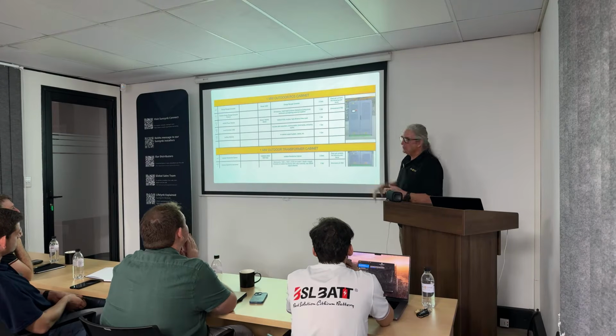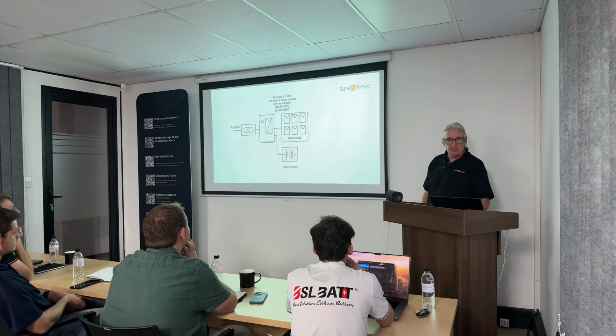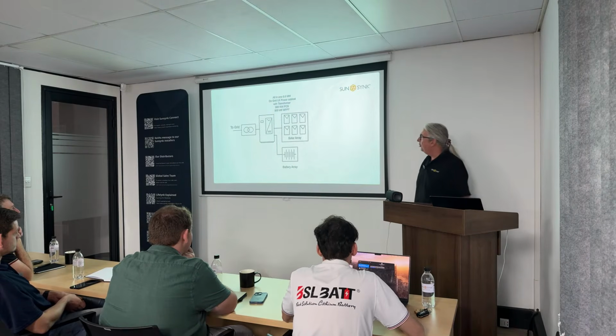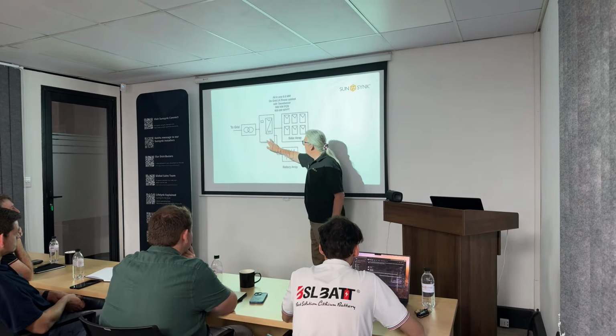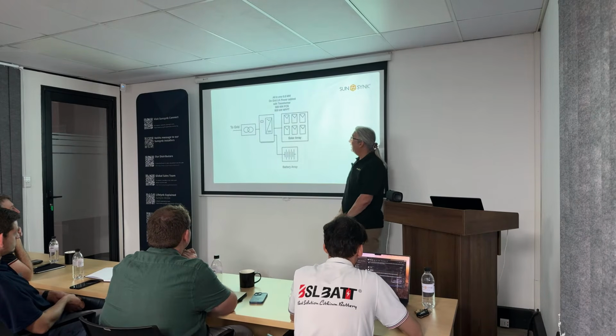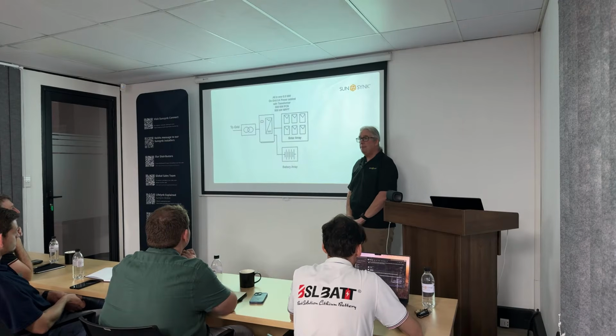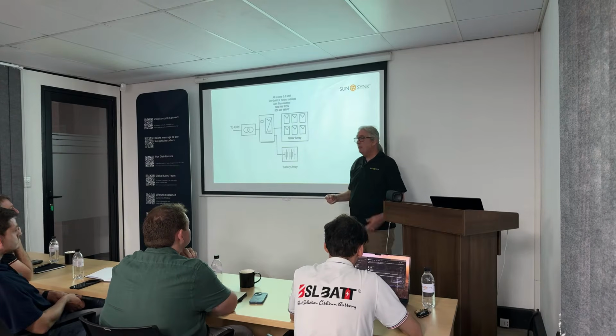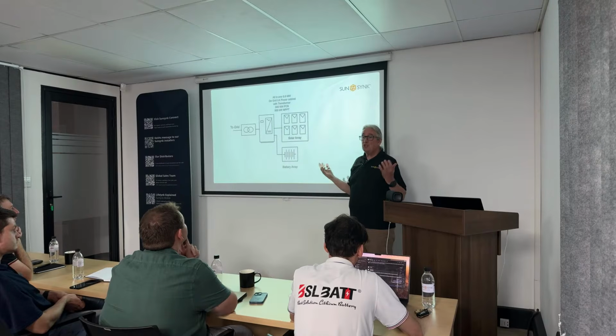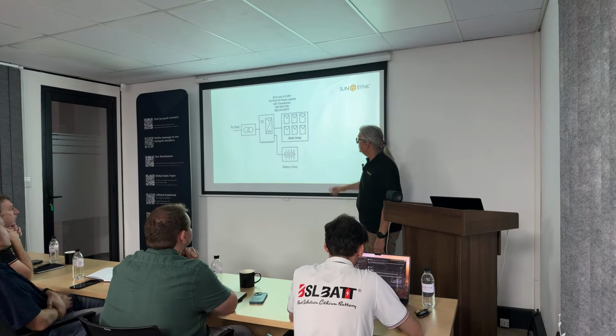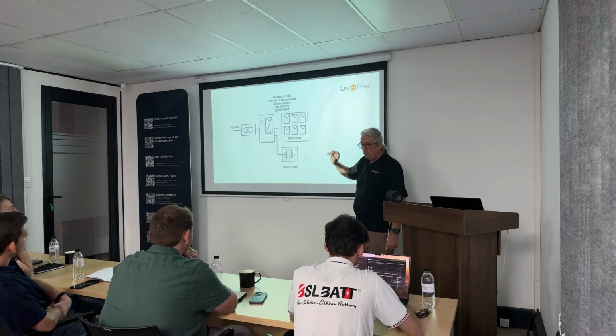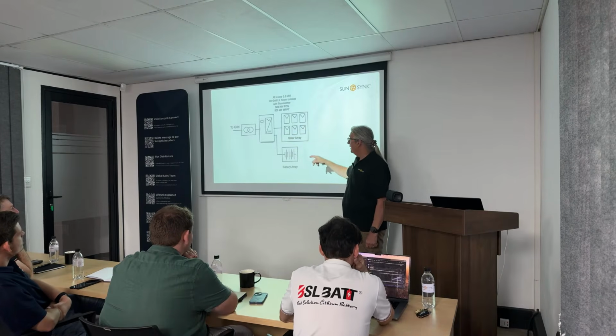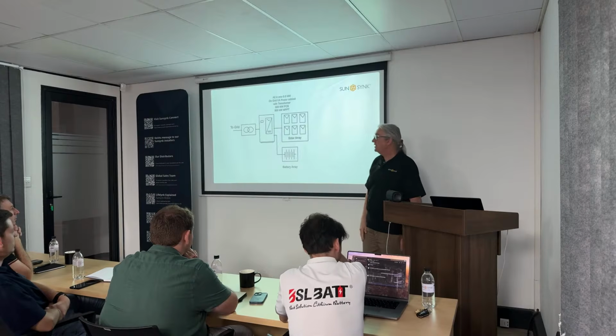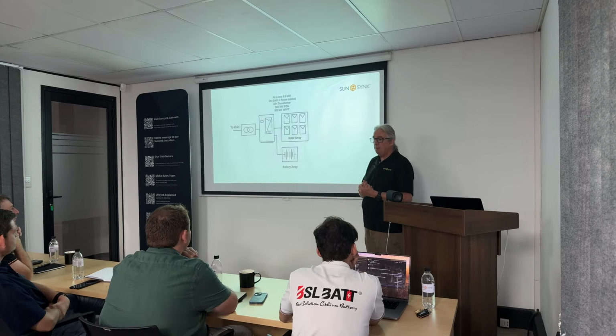But then we have modular systems, and we have several modular systems. So in its simplest form, we have here a simple on-grid module, which is a 500 kilowatt PCS, 500 kilowatt MPPT. You can have it with or without transformers on grid. So this one shows, because there's no STS on this one, solar panels work pretty much like a big string inverter in that respect. So you have solar panels, it can export if you want it to, or it doesn't have to export. It's like a big string inverter, except it can store the energy in the batteries. You can use it with or without transformer.